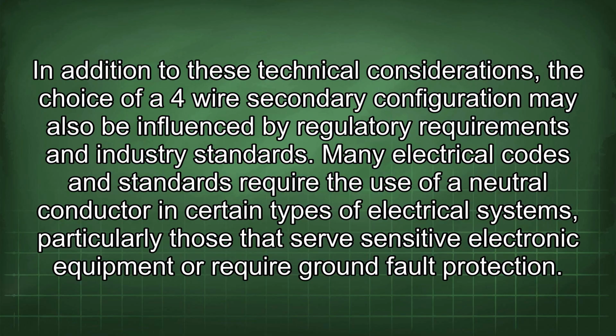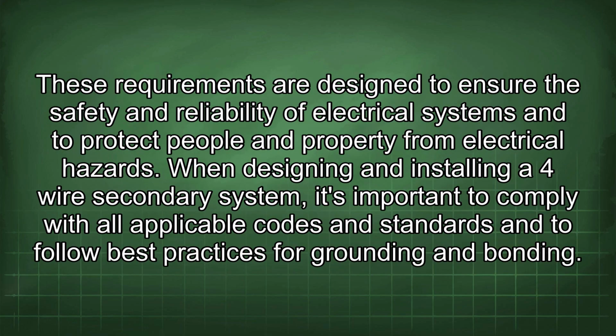In addition to these technical considerations, the choice of a 4-wire secondary configuration may also be influenced by regulatory requirements and industry standards. Many electrical codes and standards require the use of a neutral conductor in certain types of electrical systems, particularly those that serve sensitive electronic equipment or require ground fault protection. These requirements are designed to ensure the safety and reliability of electrical systems and to protect people and property from electrical hazards. When designing and installing a 4-wire secondary system, it's important to comply with all applicable codes and standards and to follow best practices for grounding and bonding.